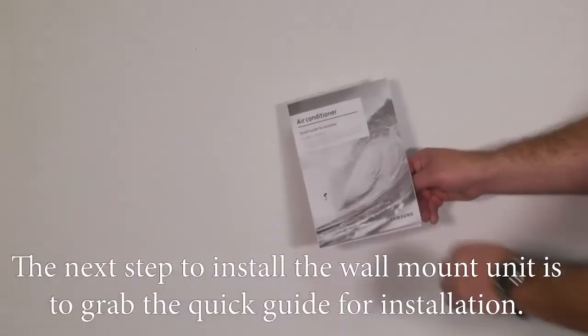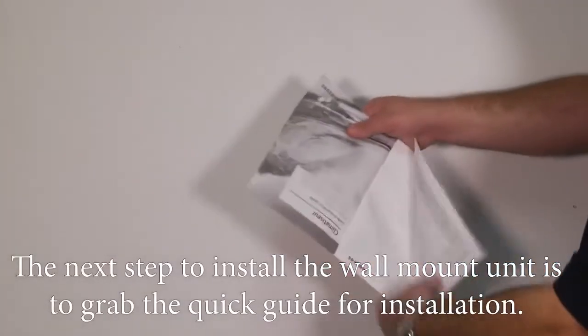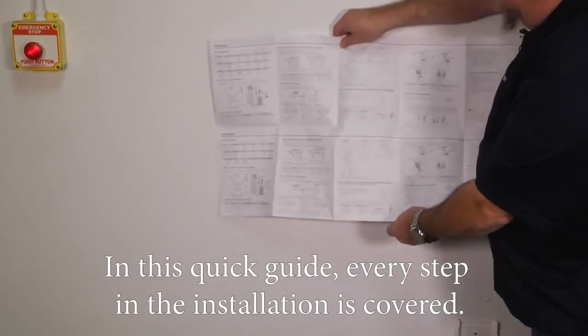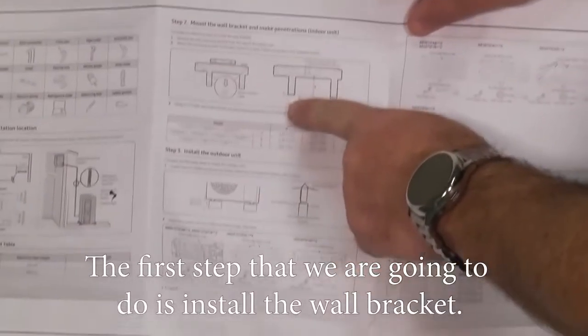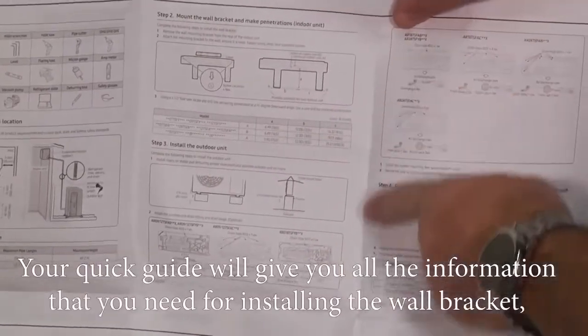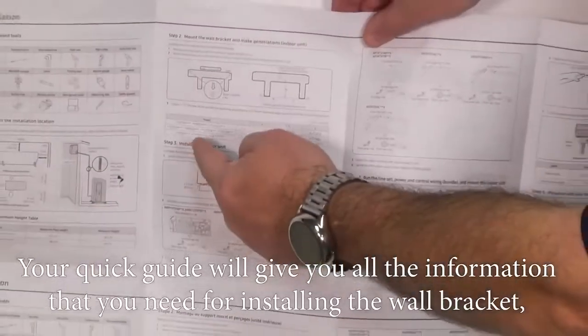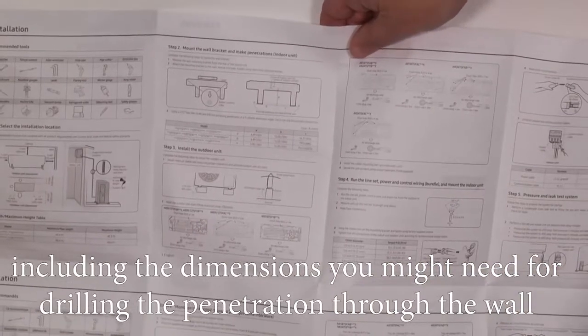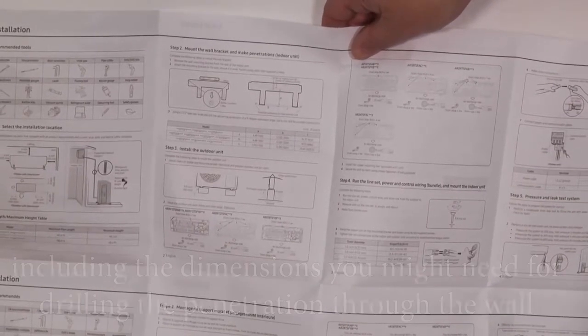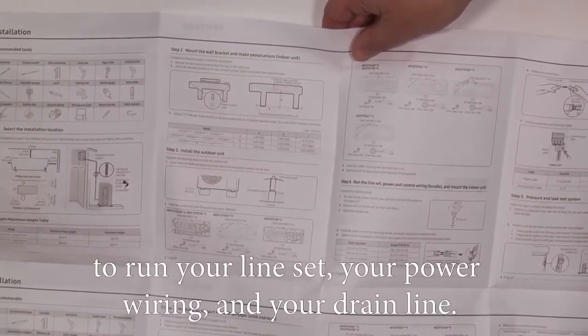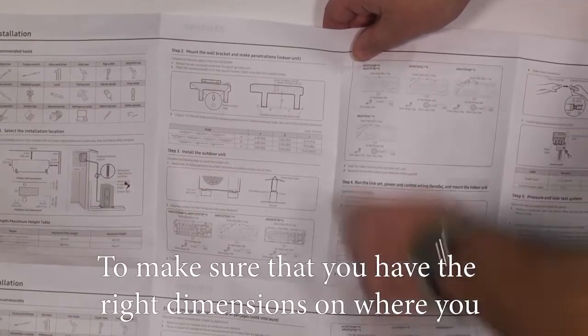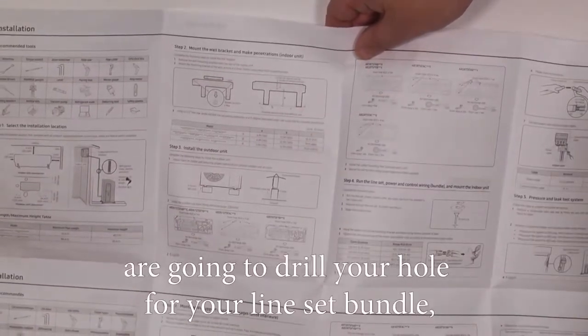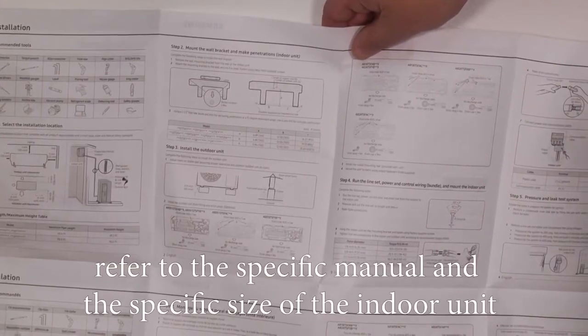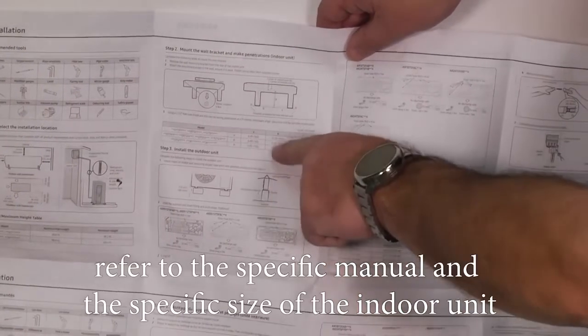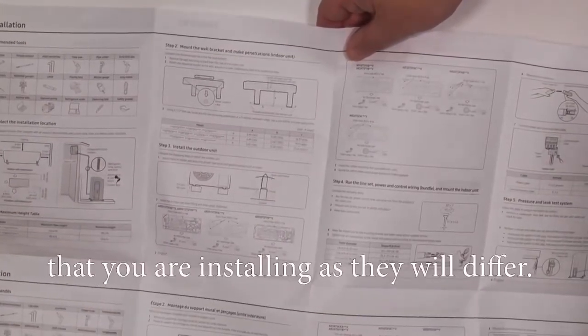The next step to install the wall mount unit is to grab the quick guide for installation. In this quick guide, every step in the installation is covered. The first step that we're going to do is install the wall bracket. Your quick guide will give you all the information that you need for installing the wall bracket, including the dimensions that you might need for drilling the penetration through the wall to run your line set, your power wiring, and your drain line. To make sure that you have the right dimensions on where you're going to drill your hole for your line set bundle, refer to the specific manual and the specific size of the indoor unit that you're installing, as they will differ.